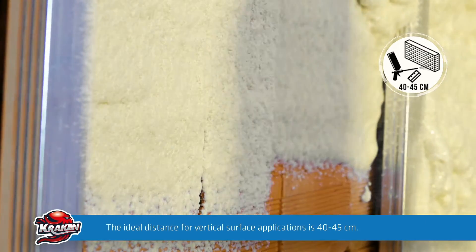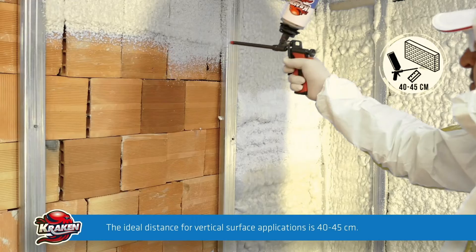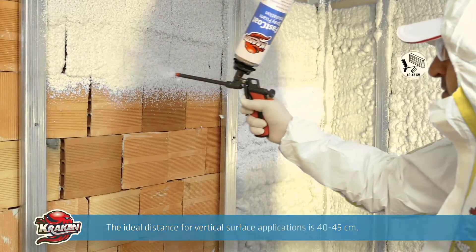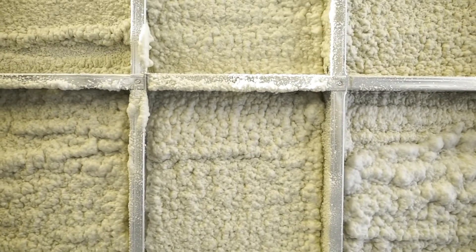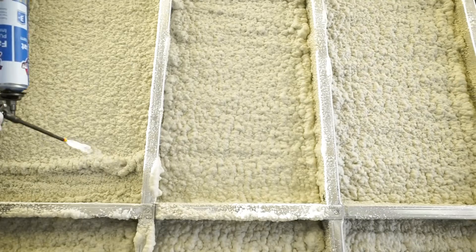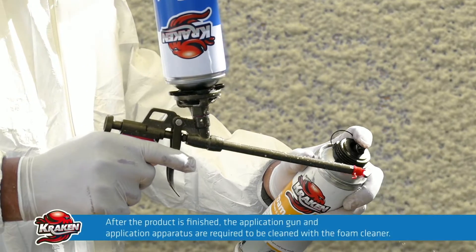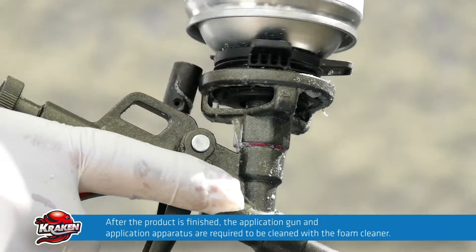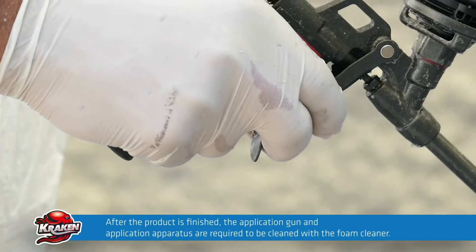Dampening the surfaces prior to the application enhances the curing rate and expansion rate. Apply the insulation foam at a distance of approximately 40 to 45 cm from the surface. Parts overexpanded after application can be trimmed, plastered and coated. After the product is finished, the application gun and application apparatus are required to be cleaned with the foam cleaner.